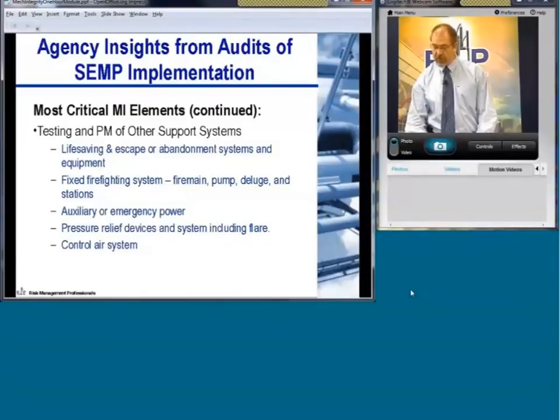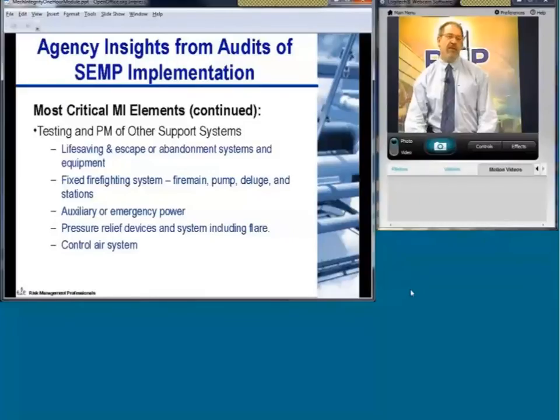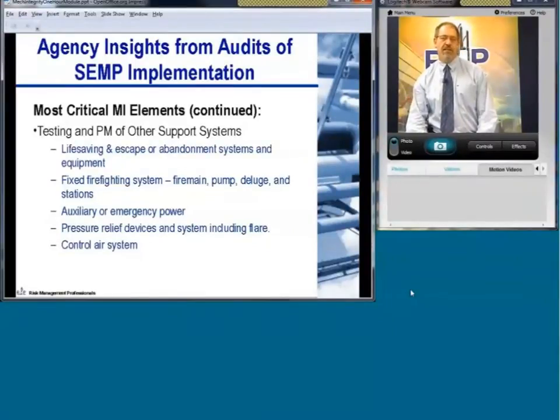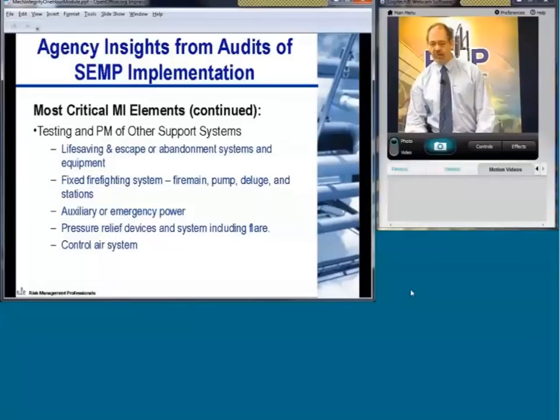Other support systems requiring periodic inspection include life-saving escape and abandonment systems: air packs, escape ropes, emergency lighting, and life rafts which have a Coast Guard-required servicing interval. For firefighting systems, there's not only the fixed fire main system with NFPA requirements, but also portable equipment serviced by outside contractors — when you turn things over to a contractor, your fire main and fire pump may not be looked at. The fire main needs periodic testing to ensure satisfactory performance. The emergency generator is sometimes forgotten: beyond periodic start-up, a full load test is required every few years. Pressure relief systems, PSVs, and flame arrester elements all have inspection and service intervals. The control air system — basic process controls and safety systems depend on clean, reliable control air.